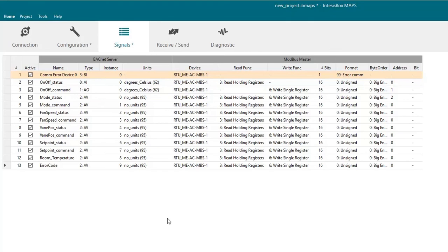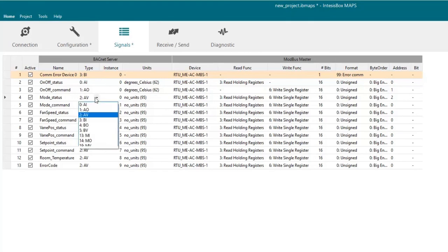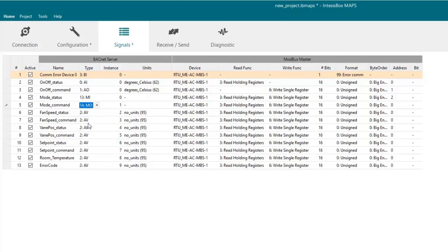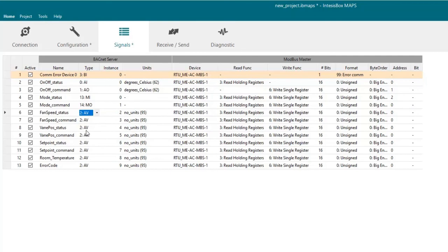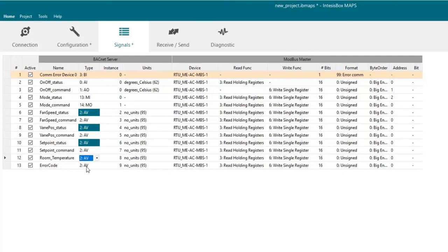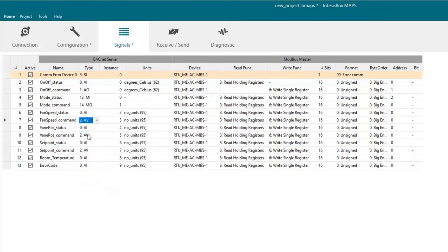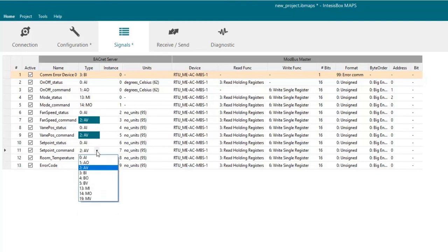Now we have to choose the right BACnet object type for each signal. Basically here we will choose multi-state input and multi-state output for the mode signals. Then all the status signals together with room temperature and error codes will be defined as analog input. And all the command signals will be defined as analog output.